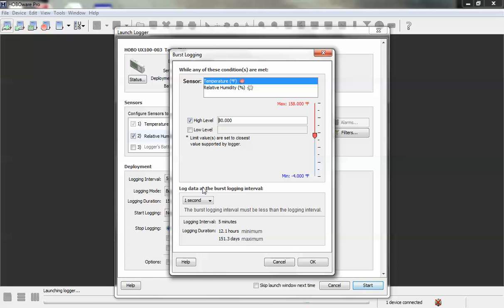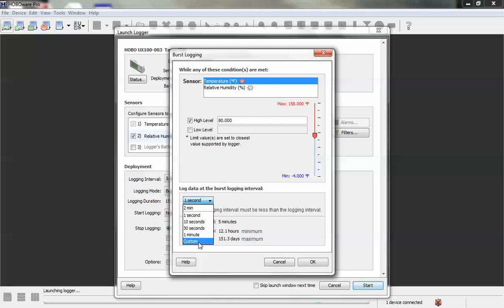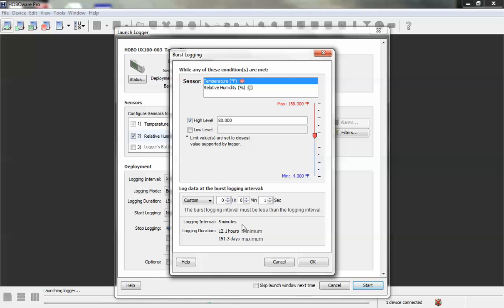And then we go down here and we configure what our burst interval would be. By default, it resets to one second. You can set it to anything within the logging interval. Obviously it's going to be less than what your logging interval is, which right now is set to five minutes.